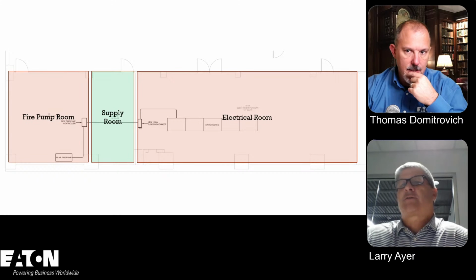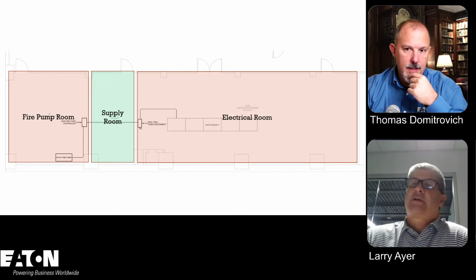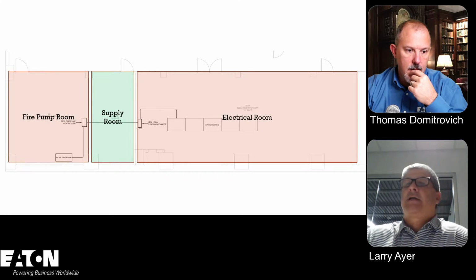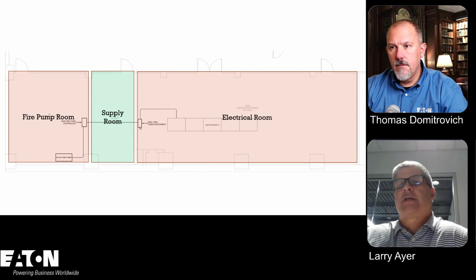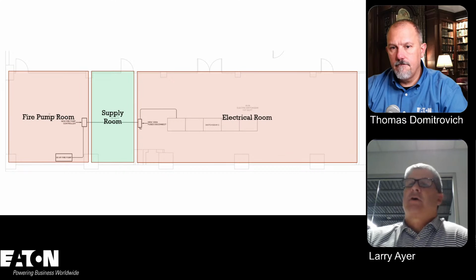So when you tap off that switchboard, set your service disconnect, and then go into the fire pump controller, do I tap off and put in my MI cable? Do I run my EMT with my Draka all the way from the switchboard? Do I splice the conductors in between and change over to my wiring method? So you have to make some decisions.